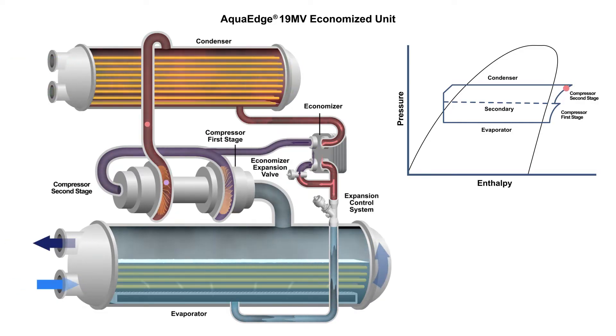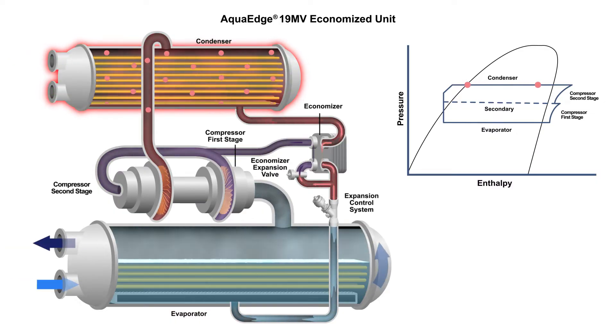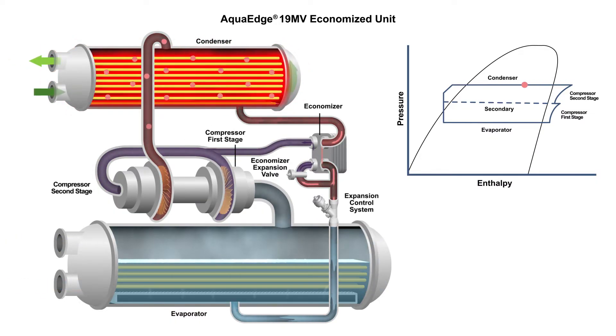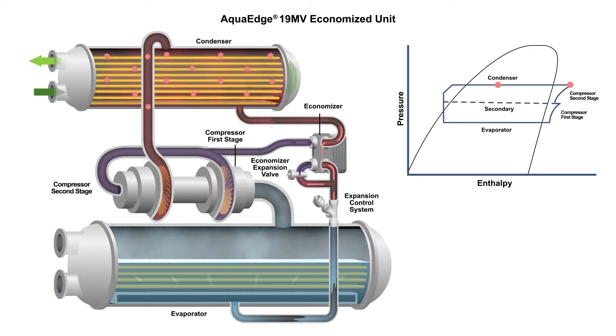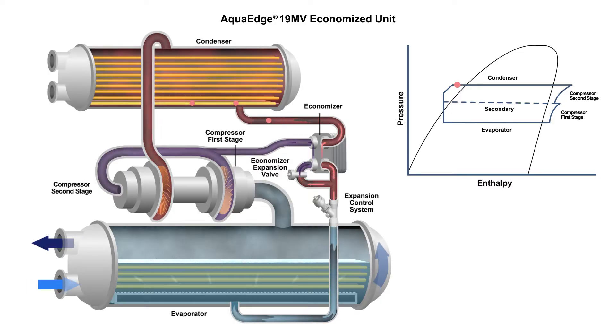The vapor now exits the second stage compressor and enters the 19MV's condenser. Water flowing through the condenser tubes removes energy from the refrigerant vapor. The vapor condenses to a liquid, collecting in the sensible subcooler at the bottom of the condenser. The subcooler extracts additional heat from the liquid refrigerant, reducing its temperature before it continues toward the economizer.